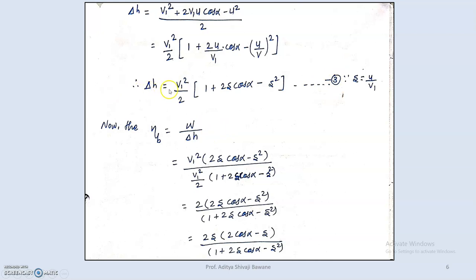Substituting work done and enthalpy drop into the blade efficiency formula: blade efficiency equals work done divided by heat drop across the stage. This gives v1 squared times (2s cos alpha − s squared) divided by (v1 squared over 2) times (1 + 2s cos alpha − s squared). The v1 squared terms cancel, leaving efficiency equals 2(2s cos alpha − s squared) divided by (1 + 2s cos alpha − s squared).